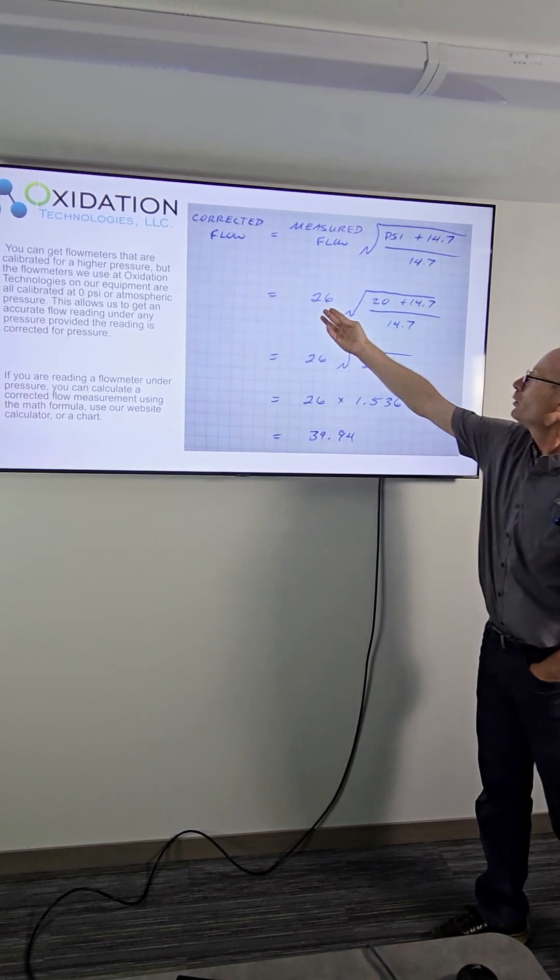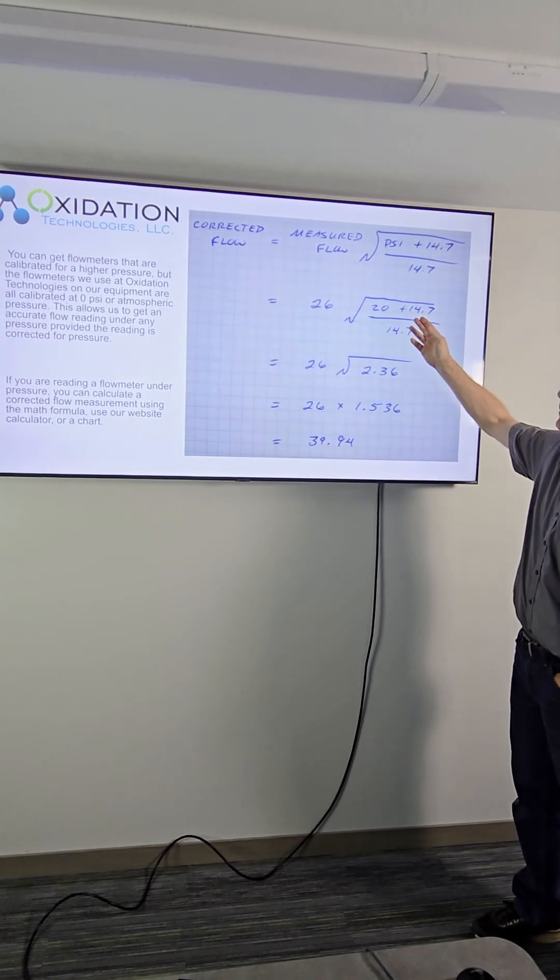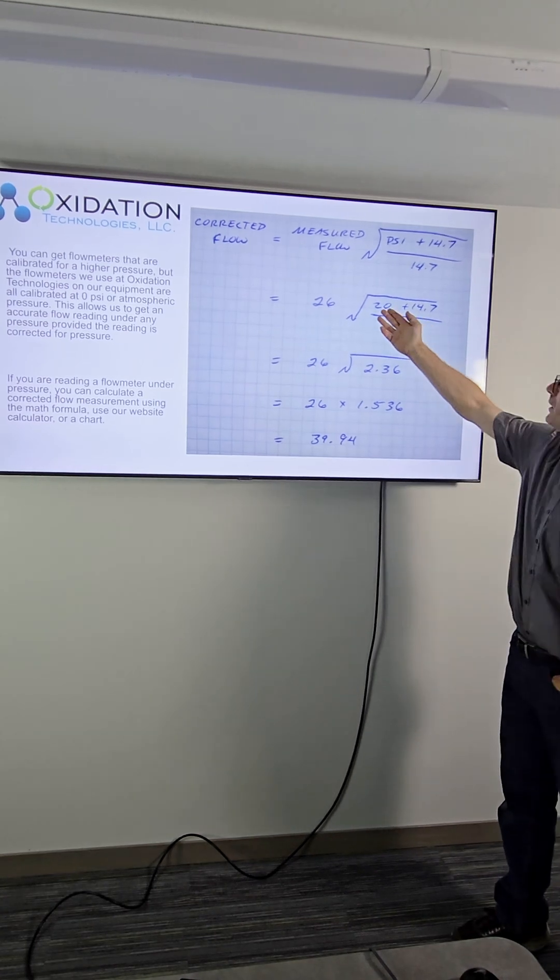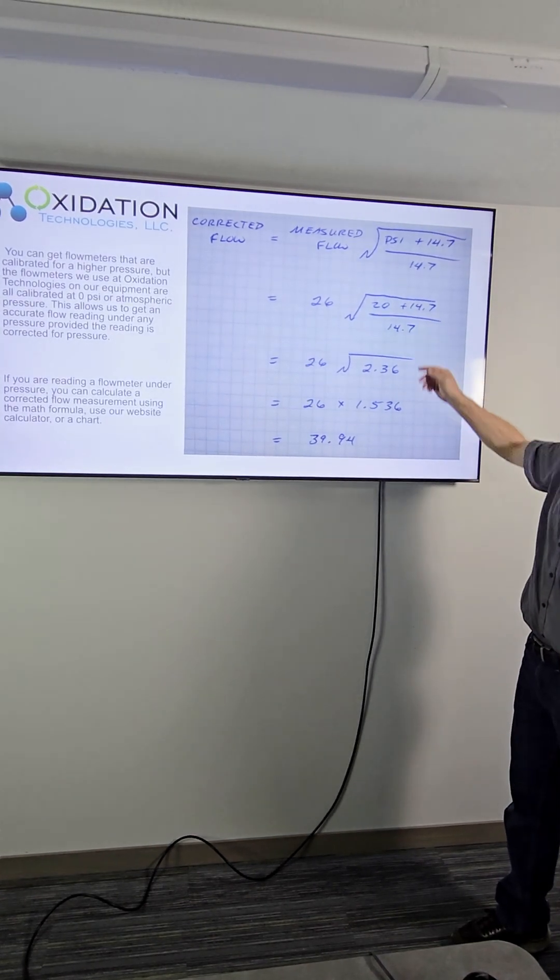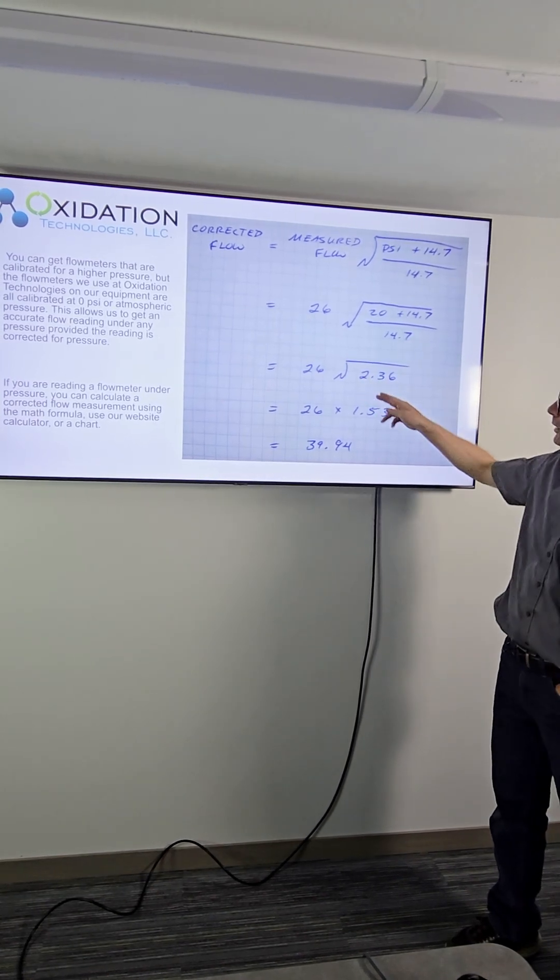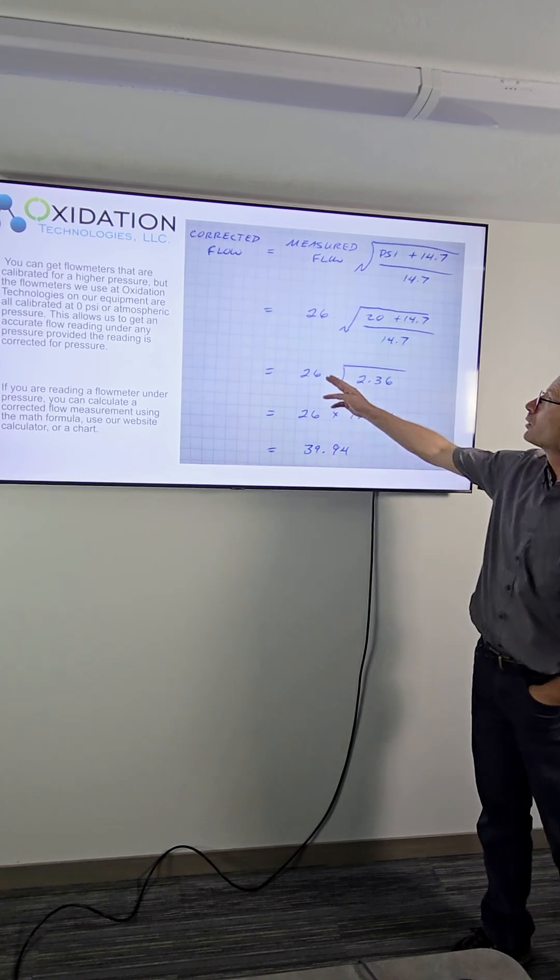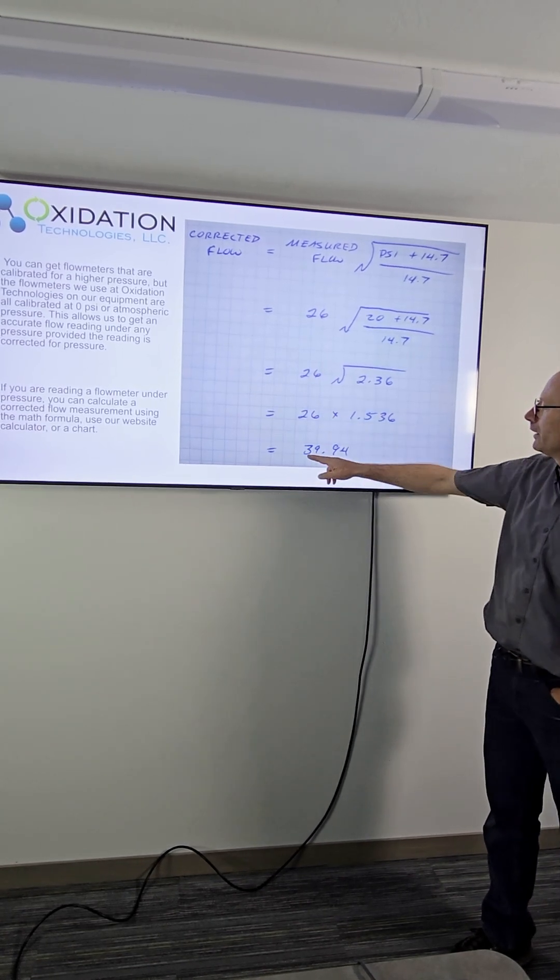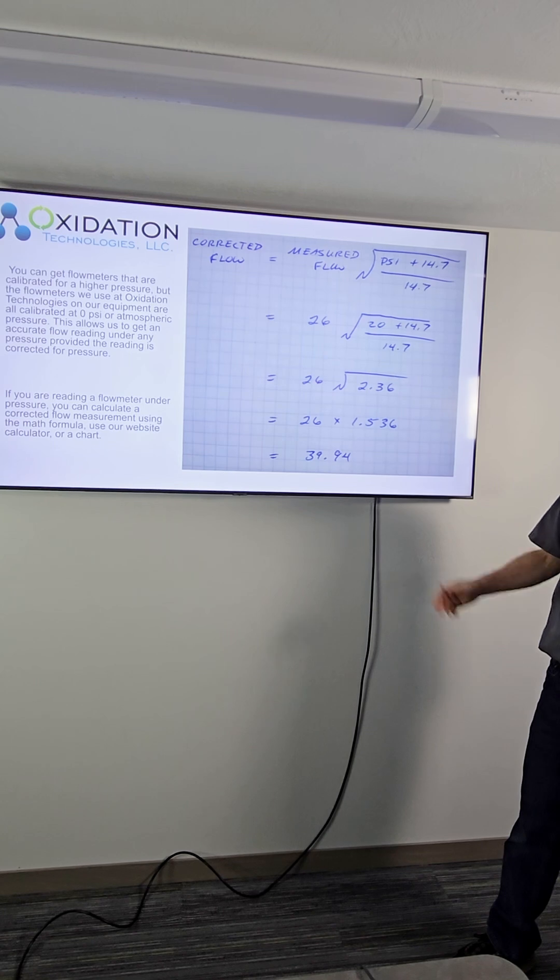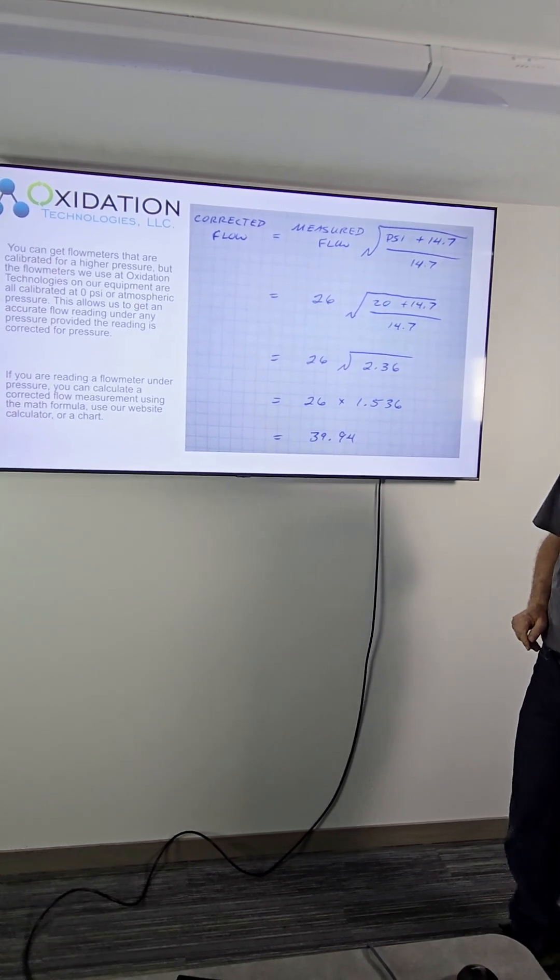So we measured 26. We put in it was at 20 psi. If you run the calculation, 20 plus 14.7 divided by 14.7 you get 2.36, take the square root of that 1.536, multiply that by the measured flow and you get 39.94 which is about exactly what it was showing on that second flow meter.